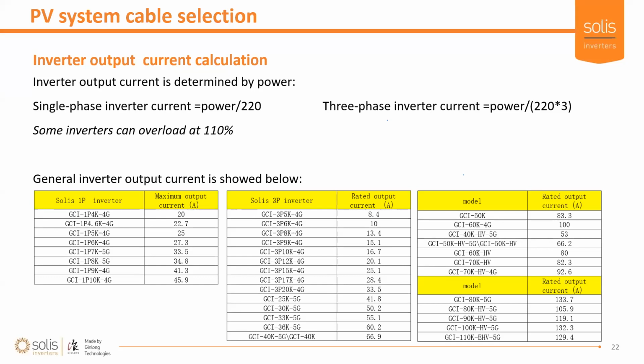For example, to ease up my brain on the math, let's consider a 6.6 kilowatt three-phase inverter. We want to know the current on each cable for that. The per phase power is that divided by 3, which is 2.2 kilowatts. Then we consider the worst case scenario voltage because we're smart, which is 220 volts. We are injecting power, so I doubt it would be that low, but let's just consider 220. You get an answer of 10 amps. So 10 amps will run through each of the conductors for that three-phase system.